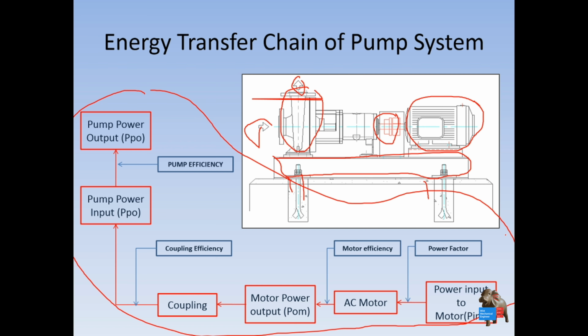The energy transfer: the power input to the motor is the electric energy transferred to the motor, and the motor will create mechanical energy, like rotation. The motor, of course, has efficiency, and the output of the motor power will be transferred to the coupling here, and then the coupling transfers the energy to the pump shaft. That is called the pump power input. Then, after the pump rotates, the pump will transfer the energy into the water flowing from the suction and finally the discharge.